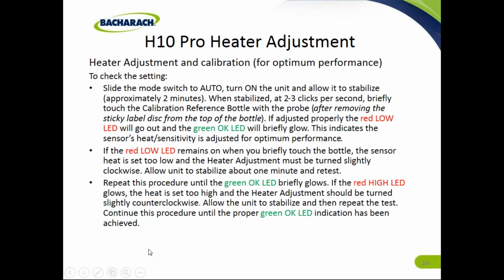Slide the mode switch to auto, turn the unit on, and allow it to stabilize for approximately 2 minutes. When stabilized at 2 to 3 clicks per second, briefly touch the calibration reference bottle with the probe, after removing the sticky label from the top of the bottle. If adjusted properly, the red low LED will go out, the green will go on, and briefly glow. This indicates the sensor's heat sensitivity is adjusted for optimum performance.